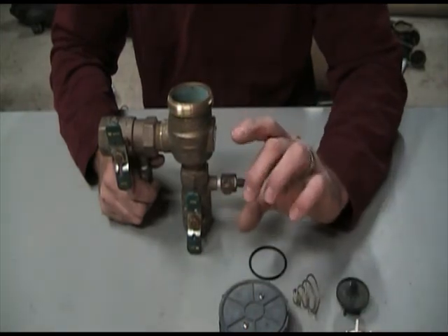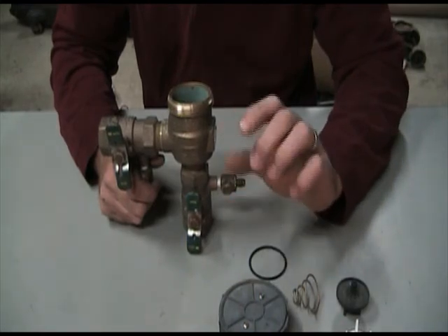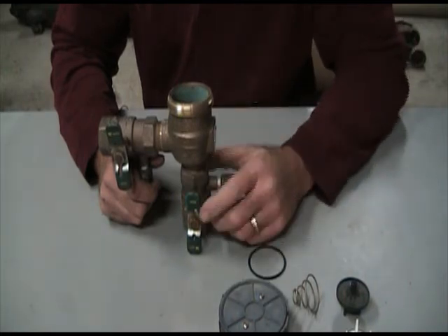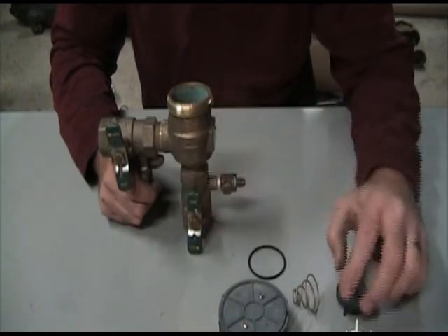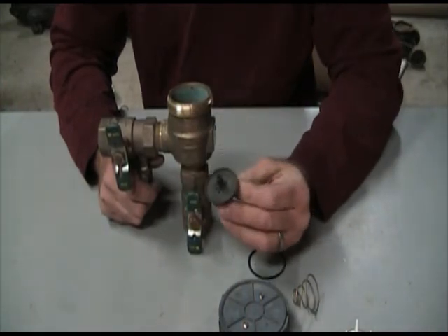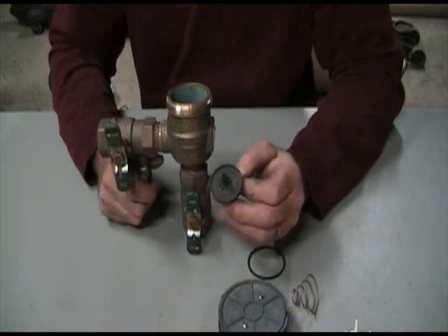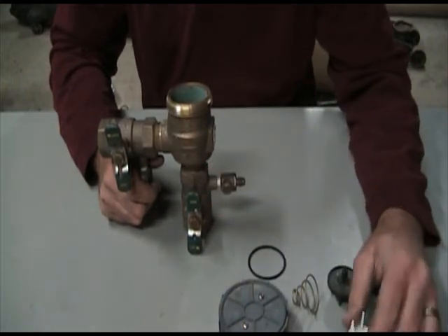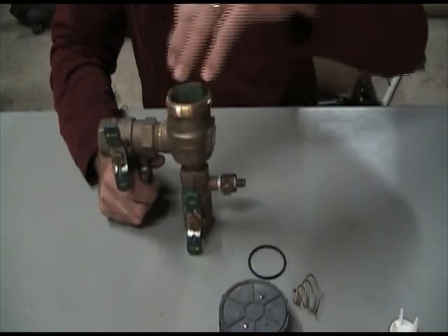The dumping mechanism, when that zone's on, sometimes they'll mess with the pressure and they'll dump water every time that zone's on. So that gives you an idea of what the purpose of this particular backflow preventer is. Now if this breaks, you'll have to buy a kit. A kit can range anywhere from $60 to $130.